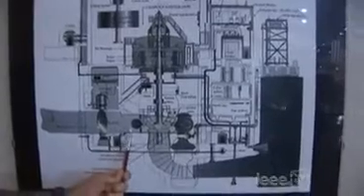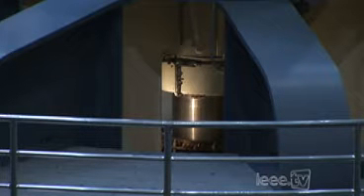As the water flows in through what's called the penstock, it goes into the scroll case, and as it goes through the scroll case it spins that turbine. The turbine is attached to the drive shaft, and the drive shaft spins the internal components of the generator — what's called the rotor and the stator.